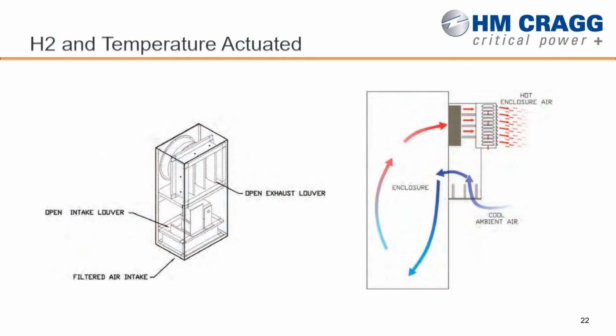So this is just kind of a quick picture. Again, it's mechanical louvers on the bottom. It's tied back through contacts to the hydrogen sensor and to the thermostat. And when those contacts close, the louvers on the bottom of the unit open, the fan actuates, and it starts bringing in fresh air.